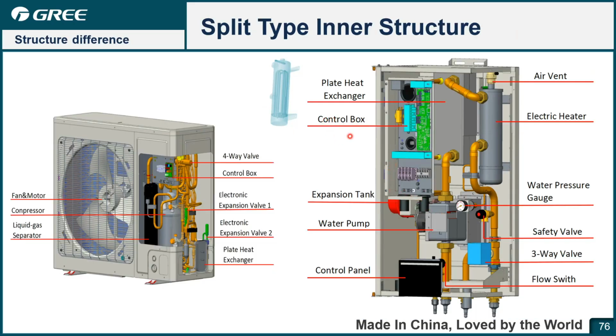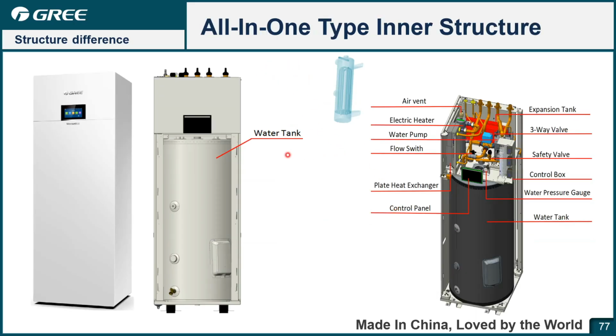And also the inner structure difference. This is a split type. You can see the refrigerant circulation is in the outdoor unit, and the heat exchange between the refrigerant and water system is in the hydro box. And there is a 3-way valve built in. And the expansion vessel is a flat rectangular expansion tank. And for the all-in-one type, the outdoor unit is the same. However, for the indoor unit, the hydro box and water tank are together, and also a 3-way valve is built in. So for this type, no need for the water connection between the hydro box and water tank.